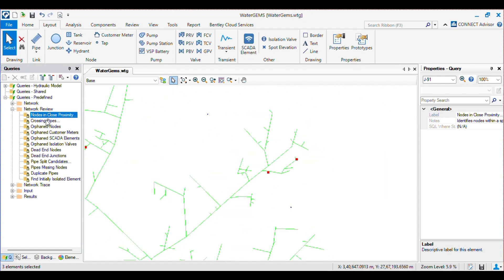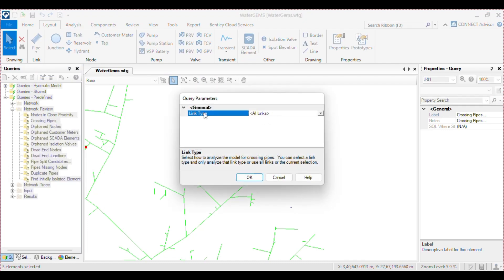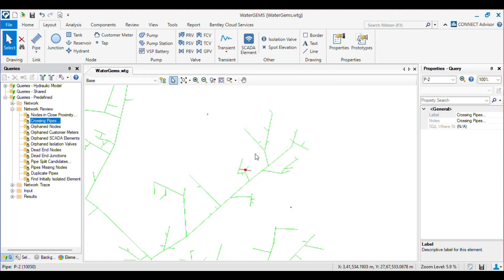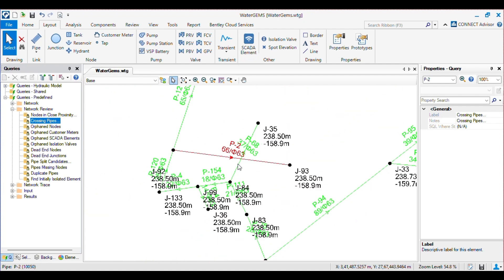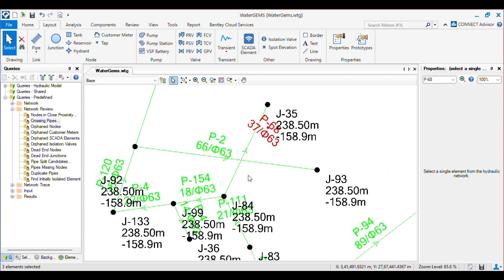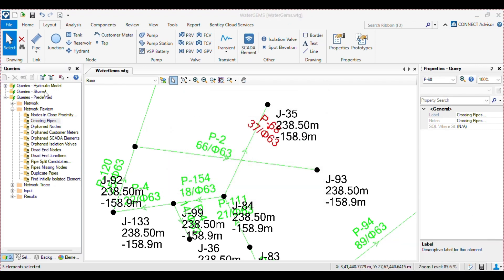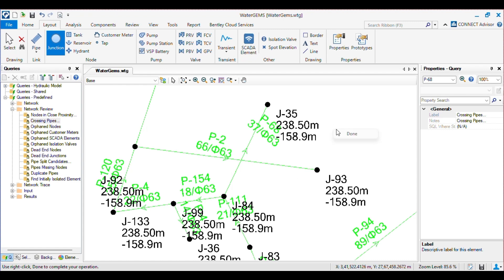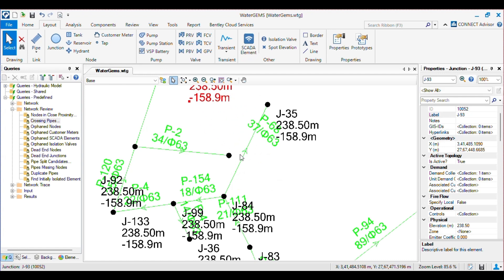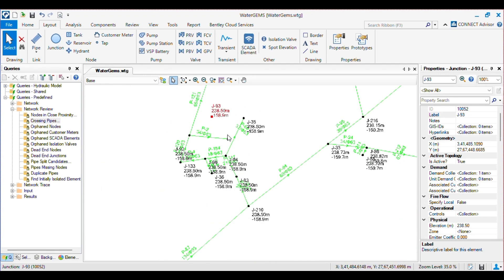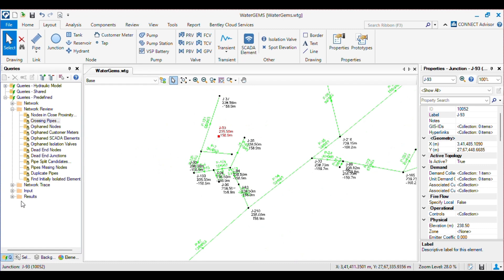Next is Crossing Pipes. For crossing pipes, if you have selection sets I will choose all the links and click OK — it will identify any pipes that are crossing and show you the result. Here you can see these pipes are crossing. By using this query you can either put a junction on the crossing pipe or simply remove the duplicate pipe. This is the benefit of the query.